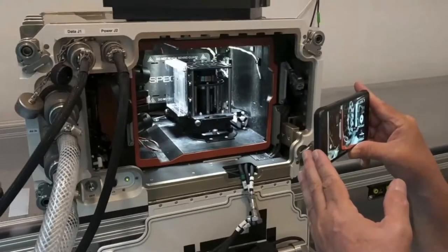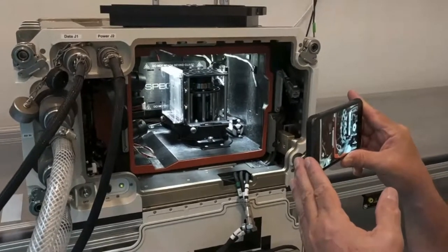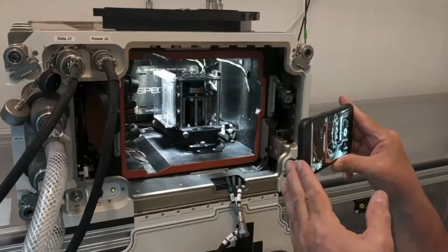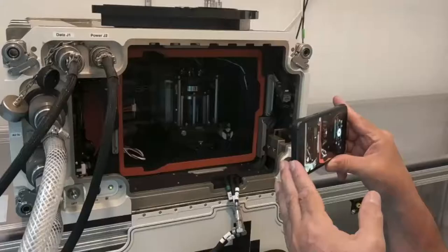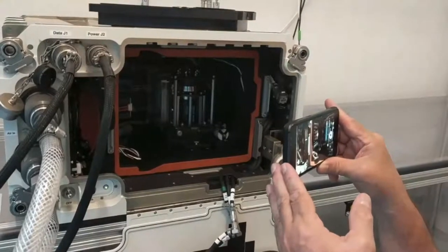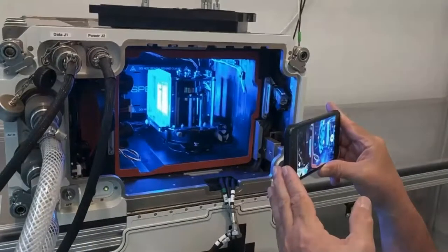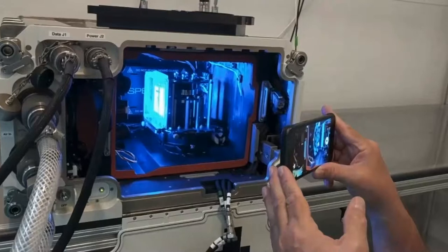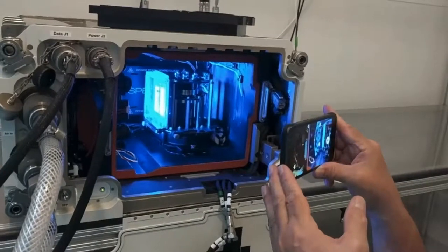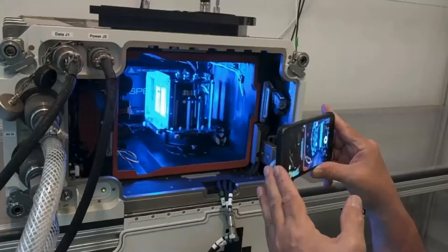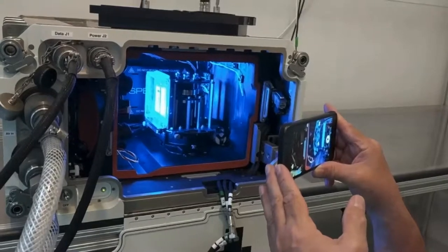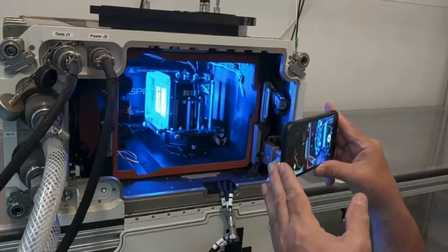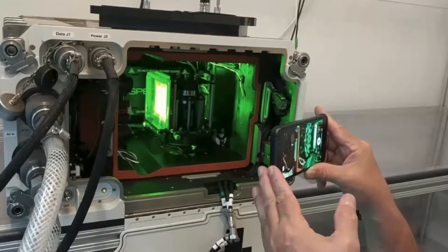Spectrum is a dissecting-level magnification fluorescent microscope designed and built for use on the ISS to image Petri plate biology. This is a custom instrument able to operate in microgravity using power and cooling resources on station. An astronaut can insert up to 4 Petri plates into a carousel inside the Spectrum and then close the door. The experiment is then run remotely from Kennedy Space Center.